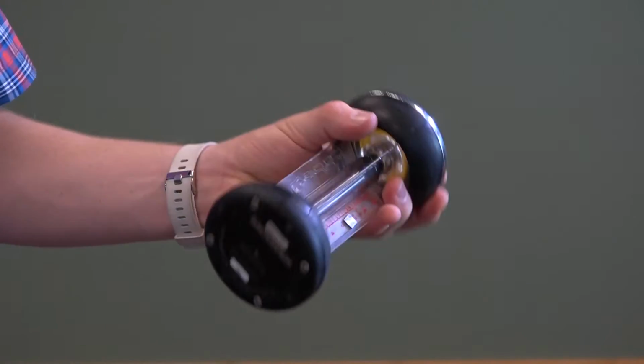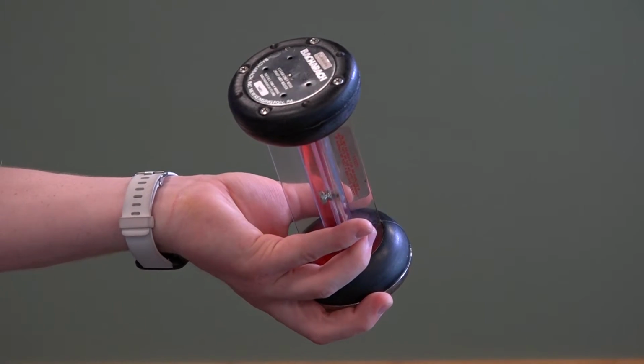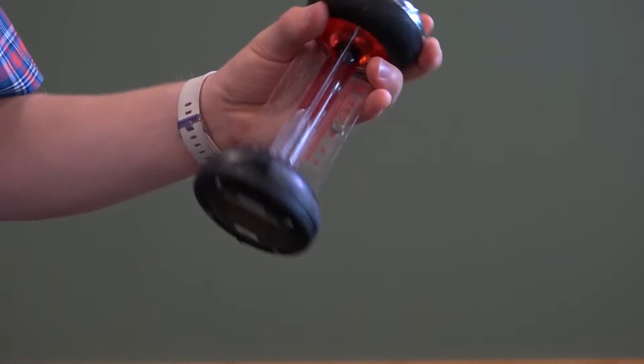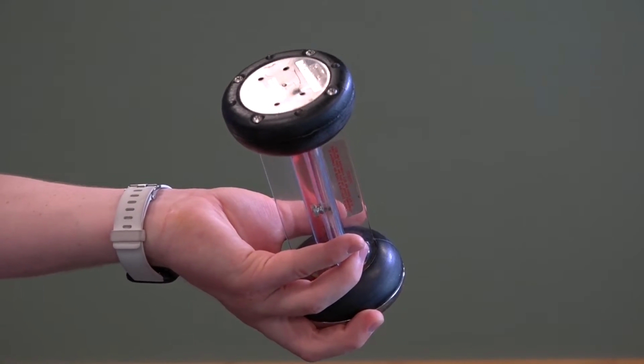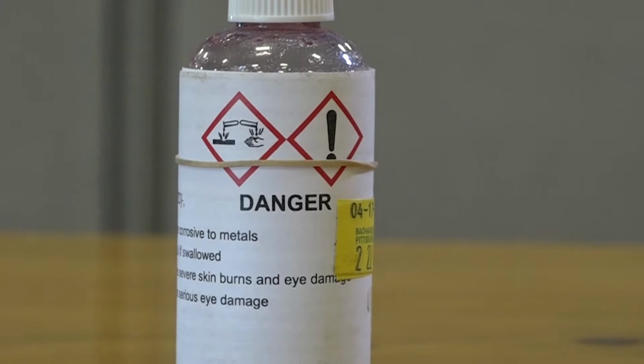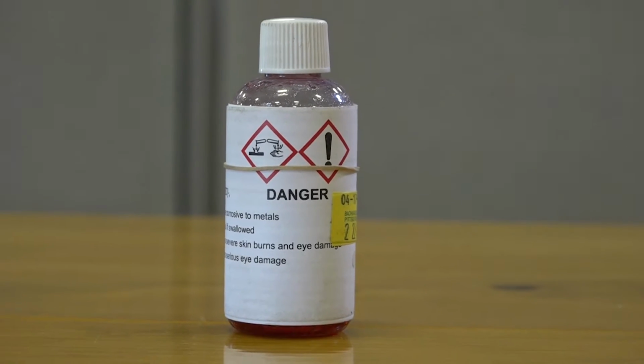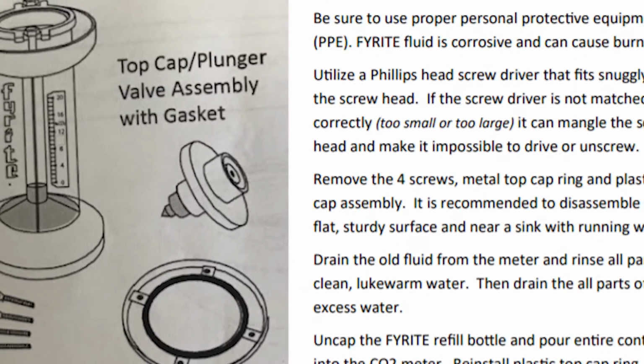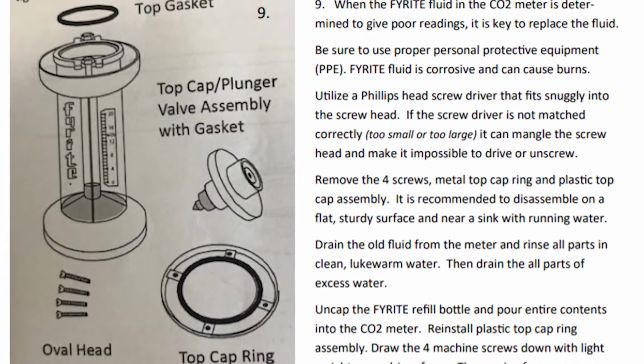Disconnect the pump and flip the meter over, allowing the solution to absorb the carbon dioxide, and then repeat the process. Exhale, pump, and flip it over. Then turn it upright. The scale should read, you guessed it, 4 to 6%. If it's not, try the process again. And if the second reading is out of range, replace the Fyrite solution. This should be rare, as the fluid will absorb carbon dioxide from over 350 samples. See the instructions for how to replace it.